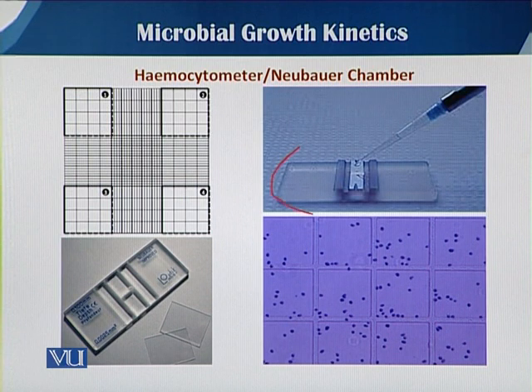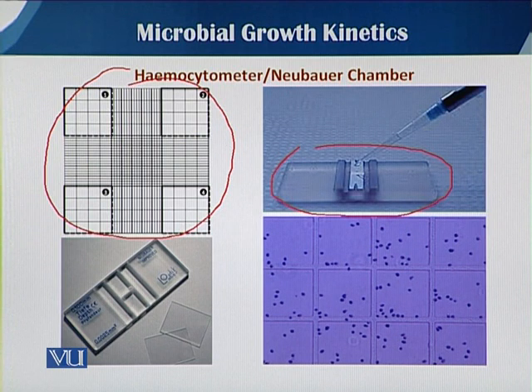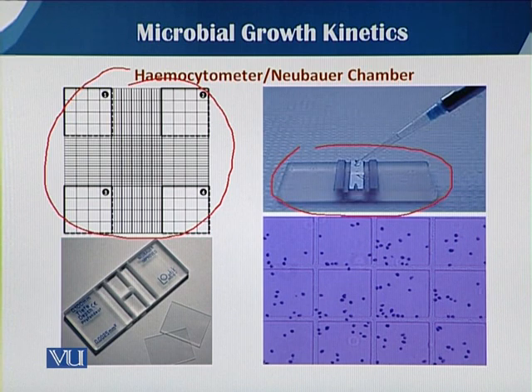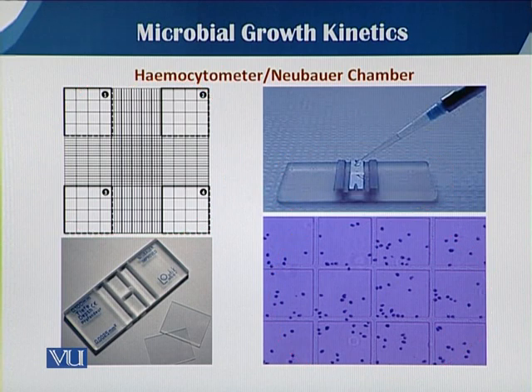In this picture you can see what a hemacytometer is. The hemacytometer is basically a glass slide in which standard cavities are formed. You can see there are different boxes — small box, medium box, and large box. The large box has a specific width, length, and depth. Most hemacytometers have a large box that is 1 millimeter long, 1 millimeter in width, and 0.1 millimeter in depth. By counting the cells in different compartments, we can estimate the total count in the culture medium.